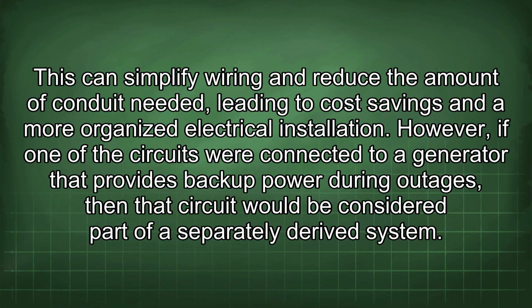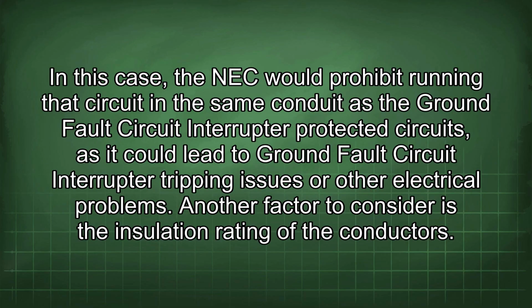However, if one of the circuits were connected to a generator that provides backup power during outages, then that circuit would be considered part of a separately derived system. In this case, the NEC would prohibit running that circuit in the same conduit as the ground fault circuit interrupter protected circuits, as it could lead to ground fault circuit interrupter tripping issues or other electrical problems.